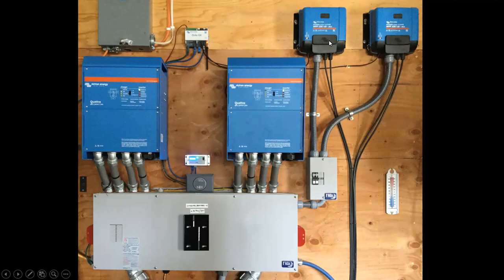With the system, we have two 250/60 MPPTs, with about 1200 watts coupled on each of those. We have overcurrent protection below that, on the battery side, and we're using MC4 cables.